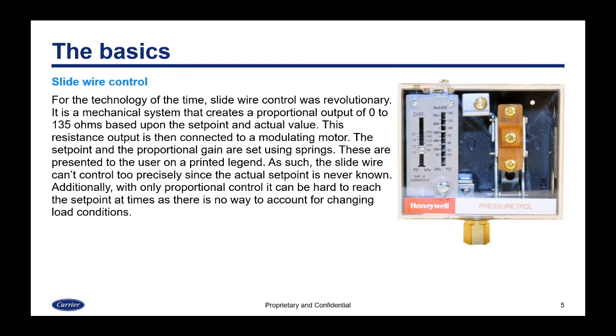For the technology of the time, slide wire control was revolutionary. It's a mechanical system that creates a proportional output of 0 to 135 ohms based upon the set point and the actual value. This resistance output is then connected to a modulating motor. The set point and the proportional gain are set using springs. These are presented to the user on a printed legend, as you can see in the image, and as such, the slide wire control can't too precisely set the actual set point or differential because the exact amount is not actually known. Additionally, with only proportional control, it can be hard to reach the set point at times as there is no way to account for changing load conditions.